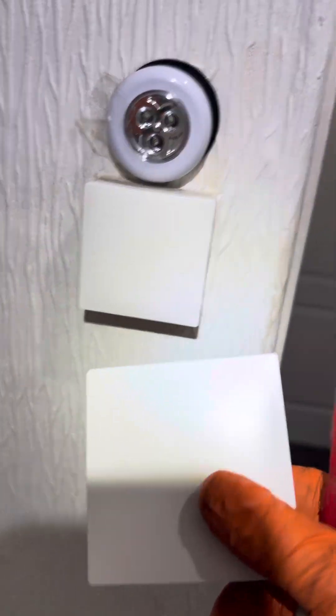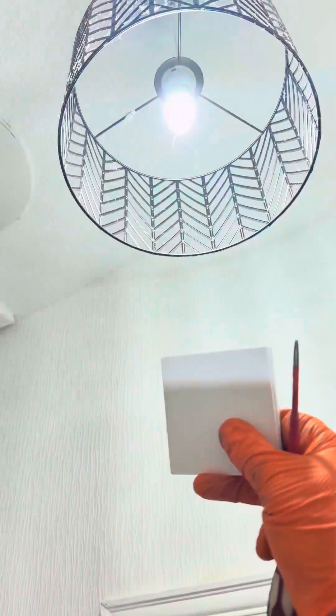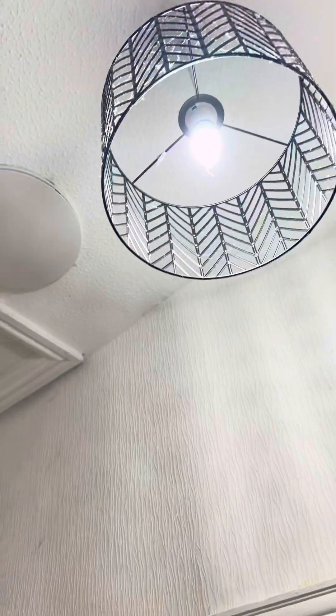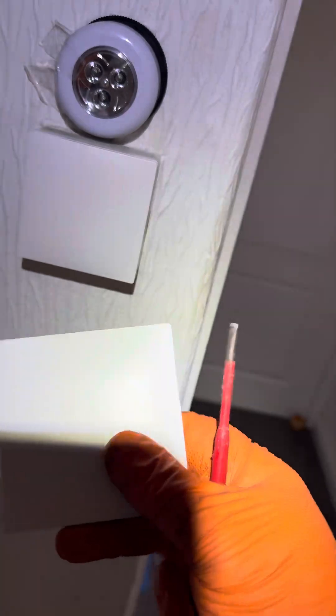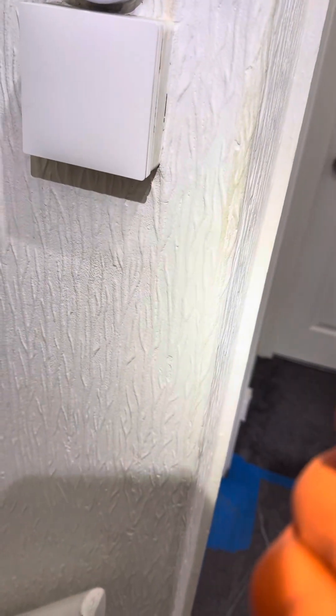Hi Teddy, so the switch down there, the wires have been cut, which I'll show you in a second. We have this, which is called a kinetic system. What that does is it's got a module up in the light fitting above and it creates a relay — no batteries required — so yeah, all sorted.